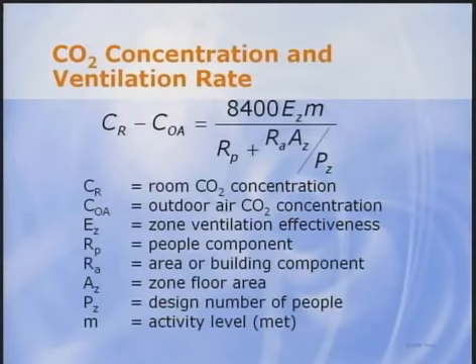Dennis discussed most of the variables. Two parts of the equation which Dennis did not discuss are M and the constant 8400. M is the activity level of the occupants, expressed in a unit called MET. And 8400 correlates CO2 concentration rate with the MET level. The room air concentration is measured with a CO2 sensor, which I'll discuss shortly.